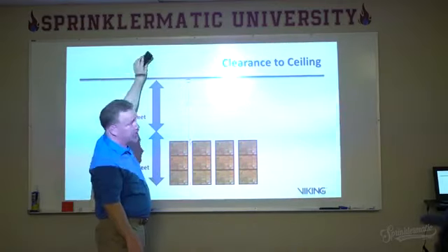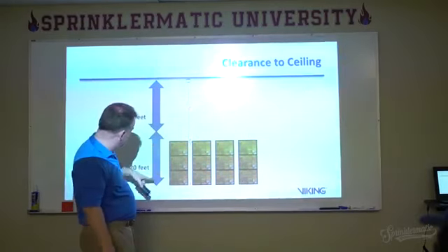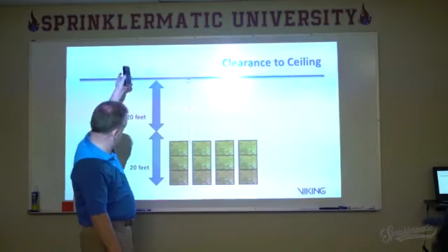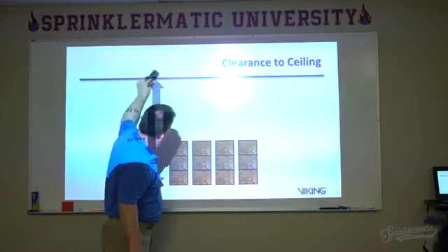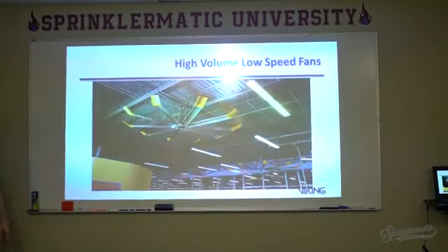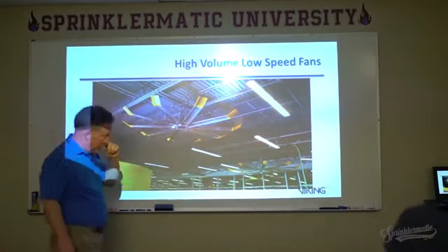If I had a 30-foot separation here, I'd need to treat that, what? As though it were 35 feet of storage. So, again, one of the interesting components here.